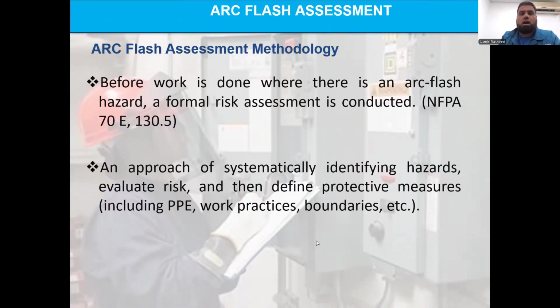That's where we talk about the arc flash assessment and the arc flash methodology. Before any work is done where there is an arc flash hazard, we need to conduct a risk assessment. That is the NFPA 70E requirement. So we systematically identify the hazard, evaluate the risk, and then decide on the protective measures, like what PPE and what category of PPE are required.